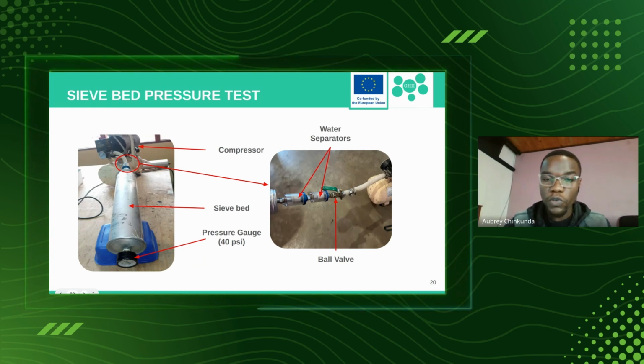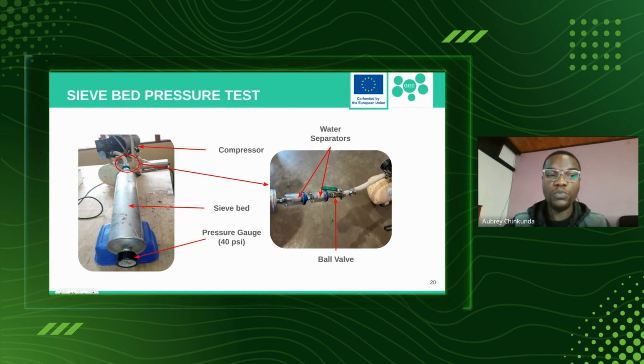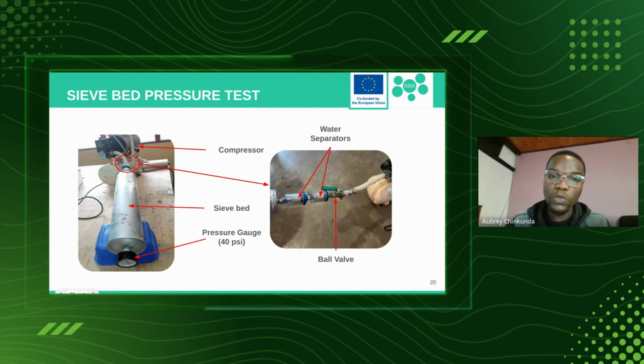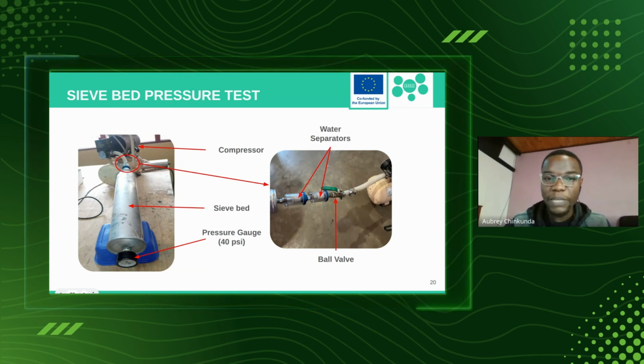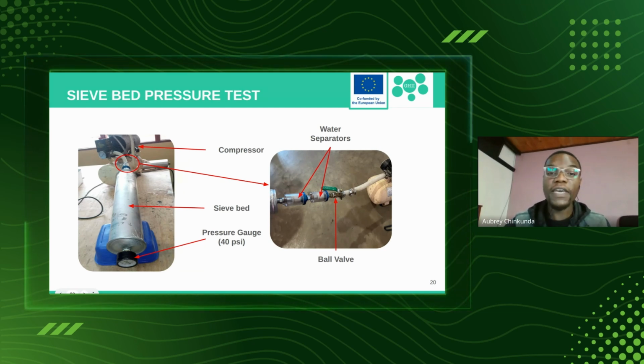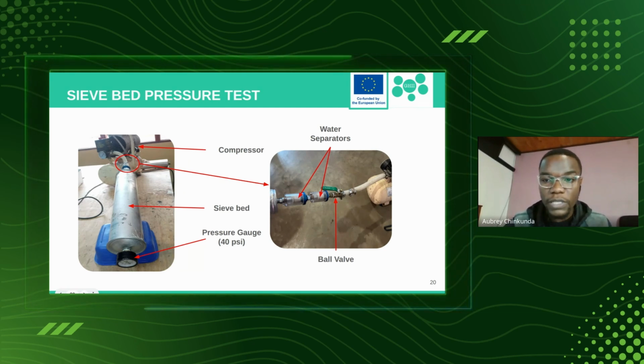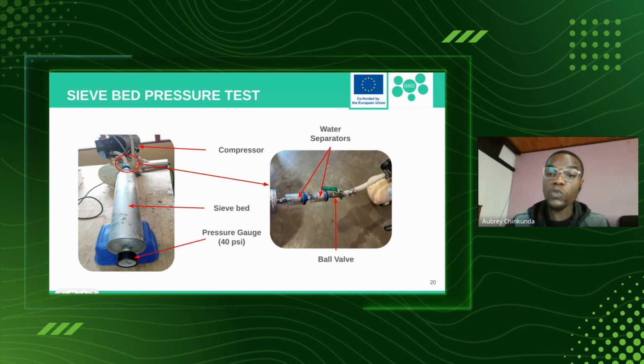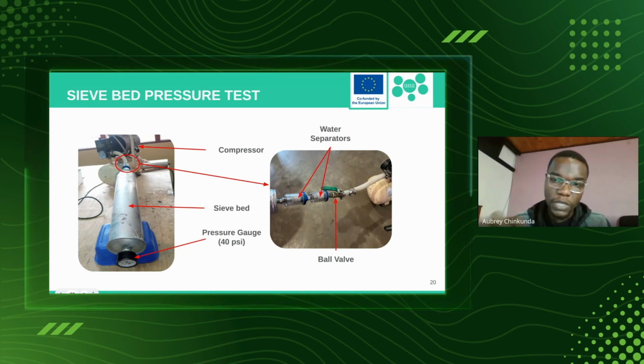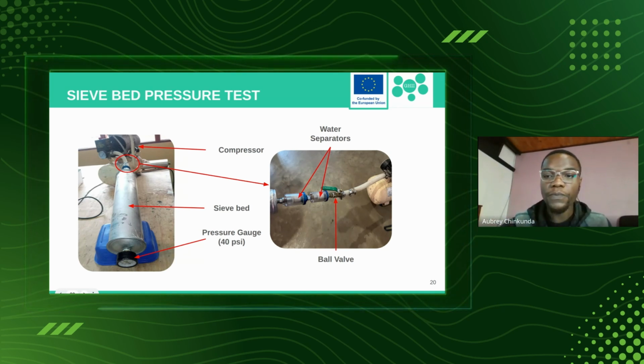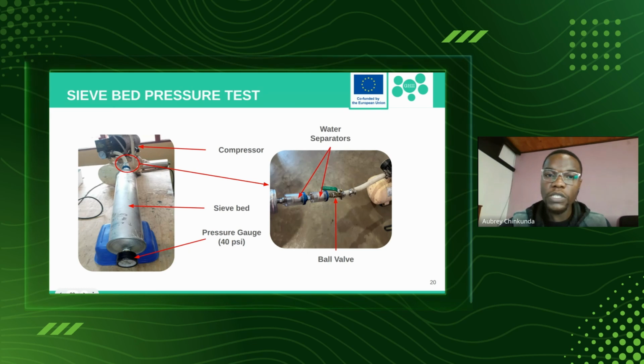And then once you turn on the compressor and you also open the ball valve, you'll be checking the pressure gauge. Once it gets to 40 psi, you close the ball valve to maintain that pressure in the sievebed. So if there are any leakages, you can notice them using some foam, some soapy water, and we take the foam and apply it on the ends of the sievebed. So if there are any leakages, you can see bubbles that will show you that there are leakages on this sievebed.